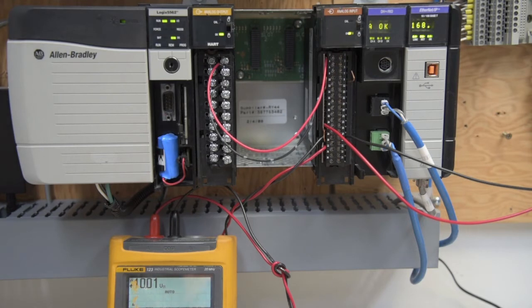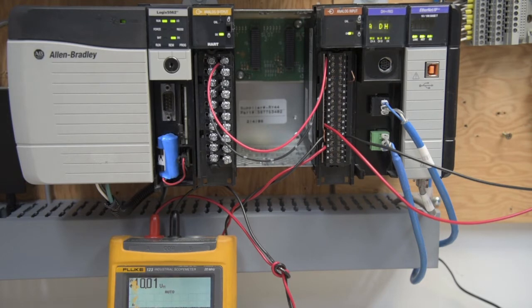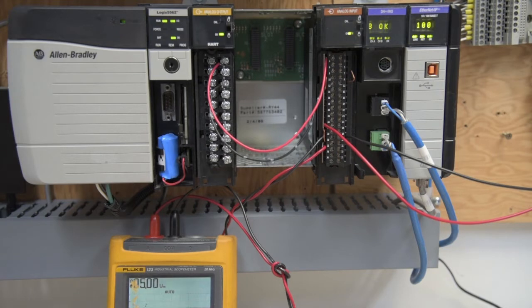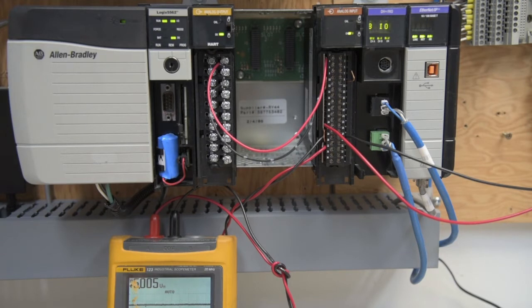set for 10 volts, and we're putting in 10.01 for our HART meter, HART analog output. Change it to plus 5, and we're at 5.005.